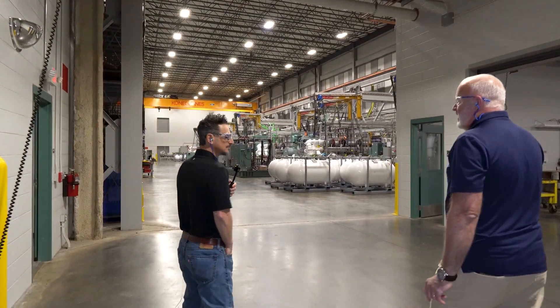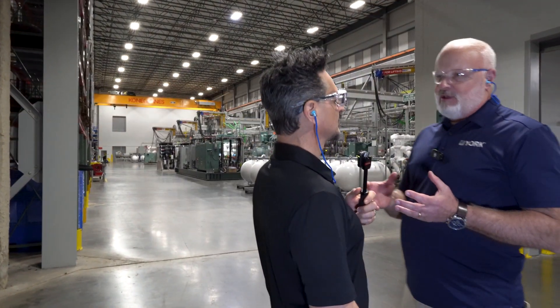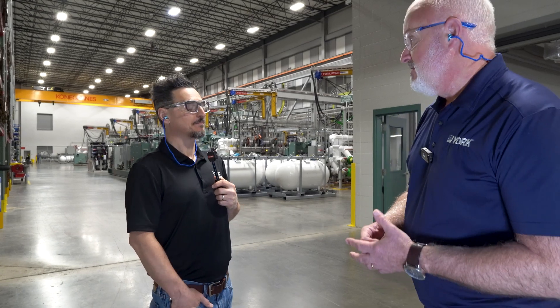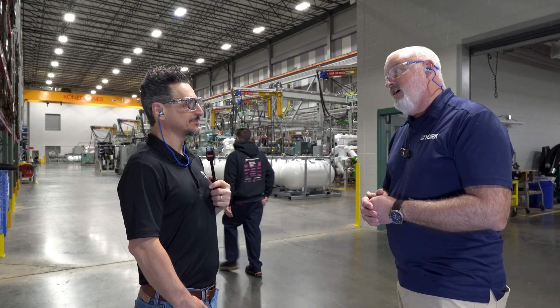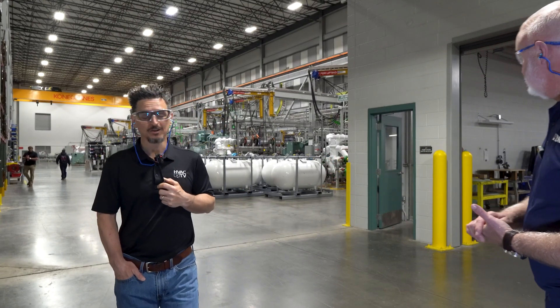And Tony, when I think about what Chad said — particularly for a new compressor — we're creating an operating map from scratch. We don't know. We have an idea. Some engineering gets us to a point that says this is where we want to be, but until Chad does his work, we don't know where we are. Just think about knowing the full limits of that compressor in only three months. Three months sounds like an awful long time, but that's a lot of data points you've got to generate to actually create that map. In the scheme of things, it's pretty short. It's amazing what goes into these.